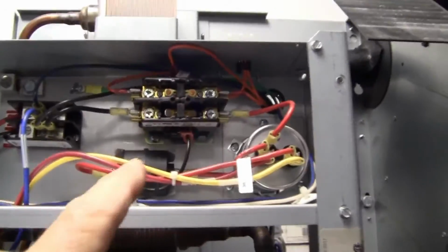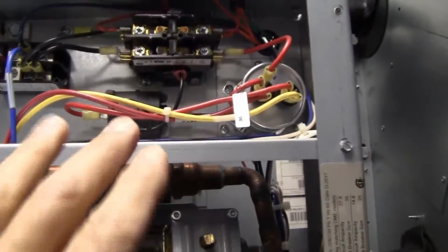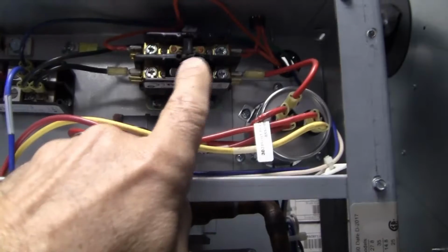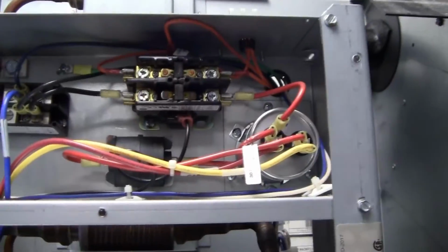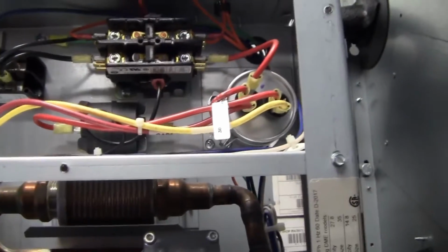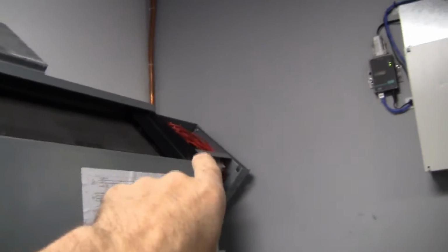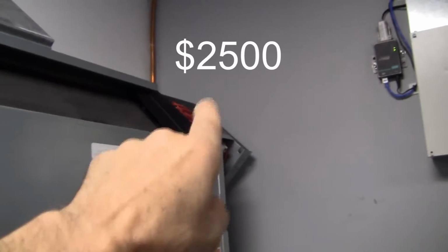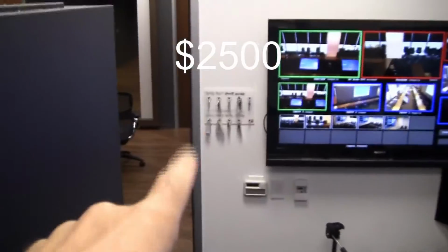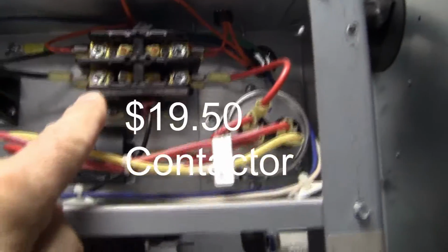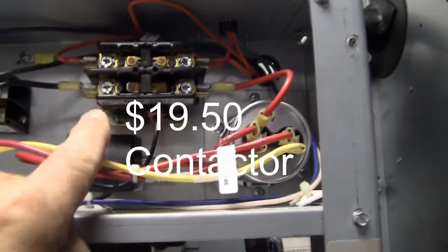So this whole troubleshooting has revealed that the complete issue is going to be this contactor coil. I'll pull this contactor coil out, we will replace it, and so forth. So we'll do that right now. Just to let you know, had it been the PC board, that PC board over there costs $2,500. Had it been that thermostat over there, that thermostat is a $1,400 thermostat. So it's real important to make sure you troubleshoot this stuff correctly. This device here, I'll probably get this contactor for 30 bucks.